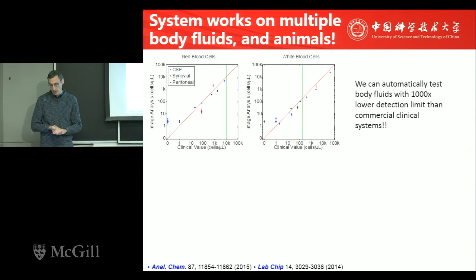So for body fluids that are very acellular, like cerebrospinal fluid or synovial fluid, the majority of clinical samples can't be counted automatically. So in a hospital like the UC Davis Hospital, they might get 100 such body fluid samples a day, and there's someone whose job it is to just spend all day looking through the microscope and counting these samples by hand. So in fact, our system can accurately count these samples with a limit of detection basically 100 to 1,000 times lower than commercial clinical systems.